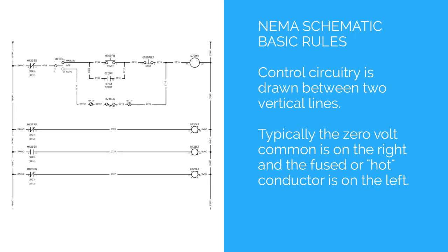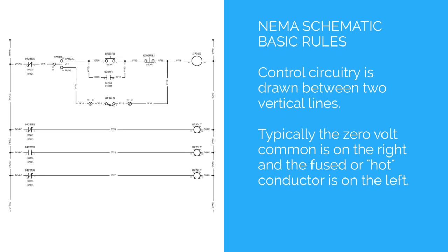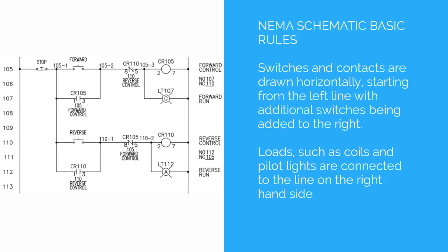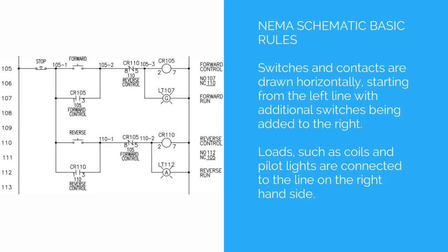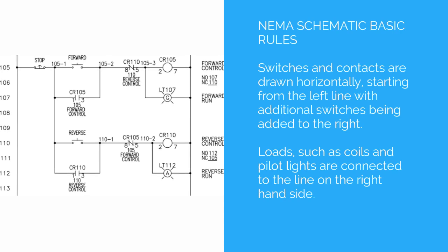NEMA schematic basic rules: control circuitry is drawn between two vertical lines. Typically the zero volt common is on the right and the fused or hot conductor is on the left. Switches and contacts are drawn horizontally, starting from the left line with additional switches being added to the right. Loads such as coils and pilot lights are connected to the line on the right-hand side.